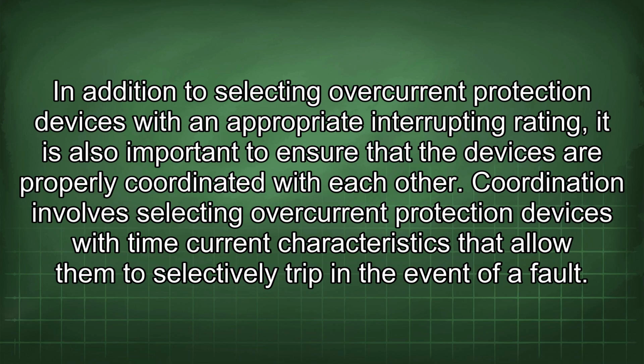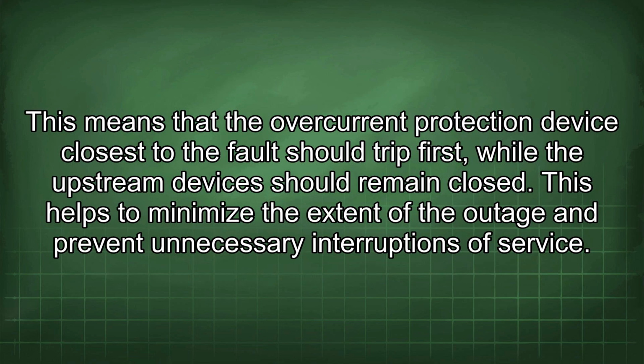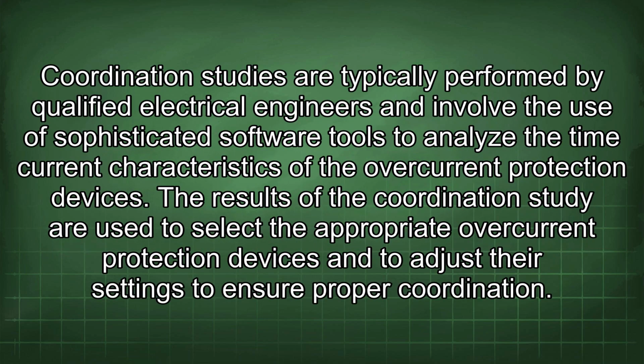Coordination involves selecting overcurrent protection devices with time current characteristics that allow them to selectively trip in the event of a fault. This means that the overcurrent protection device closest to the fault should trip first, while the upstream devices should remain closed. This helps to minimize the extent of the outage and prevent unnecessary interruptions of service. Coordination studies are typically performed by qualified electrical engineers and involve the use of sophisticated software tools to analyze the time current characteristics of the overcurrent protection devices.